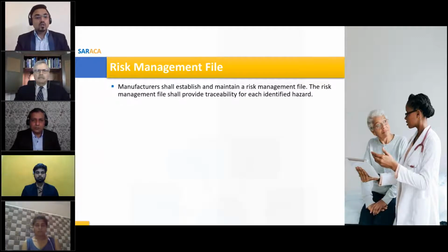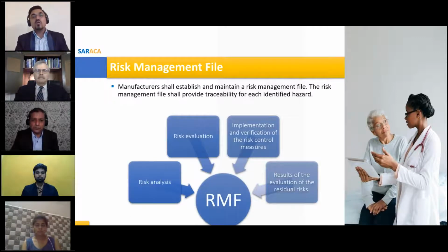So what documentation are you going to keep in the risk management file? All types of risk analysis documents, all risk evaluation documents, then all the verification documents of your implemented risk control measures: the implementation process and all the verification processes of the risk control measures. Then the results of the evaluation of the residual risks: how you are evaluating, how you are estimating, what the results are, and what the final residual risks are. All those documents need to be documented in your RMF, that is, the risk management file.